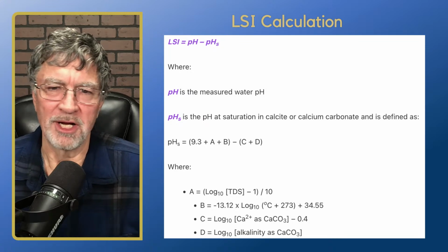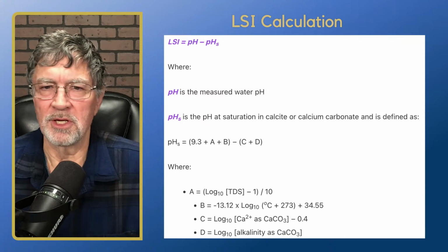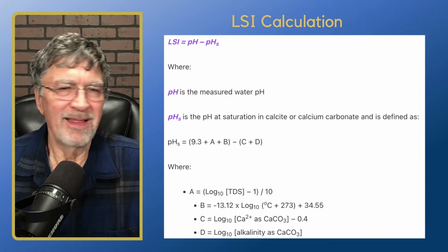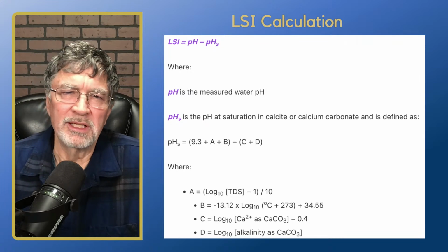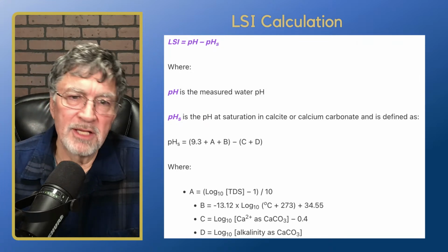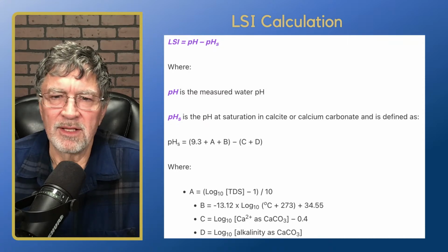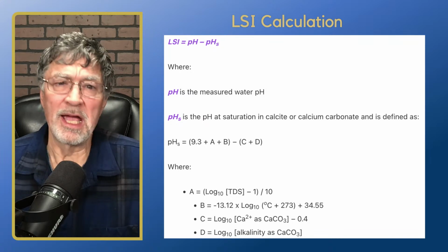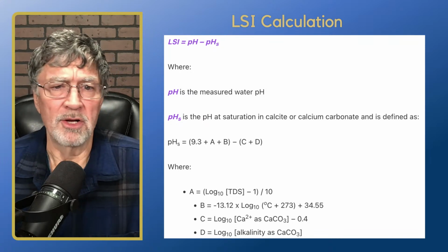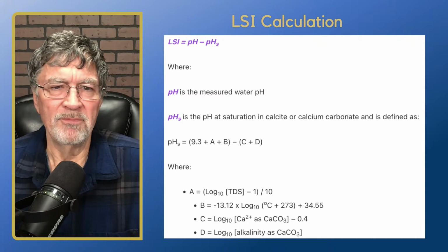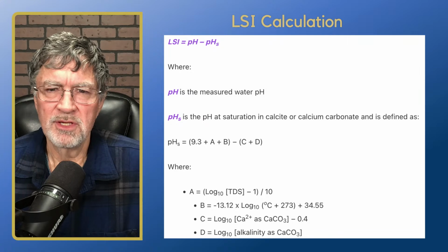Even if you throw it on ice, it may be colder than what you collected the temperature at, so the temperature is going to change a little bit. That's not the huge variable in LSI, but it can change the numbers a little bit. Whether the pH degrades over time, things come out of saturation, you get some degassing, that can cause things to get a little more acidic. So sending it to the lab definitely has a few caveats.